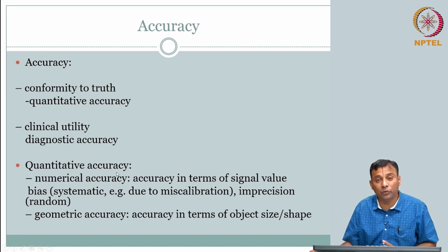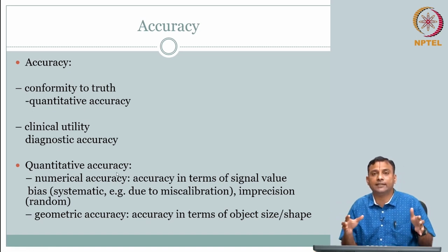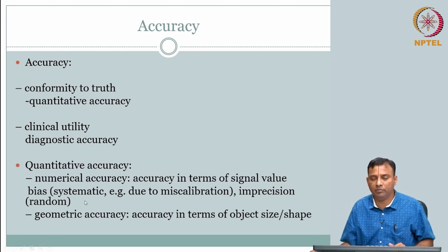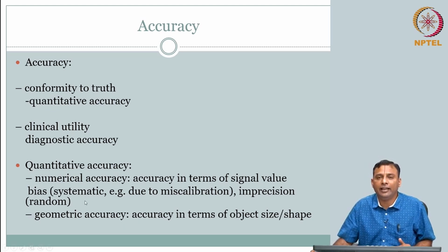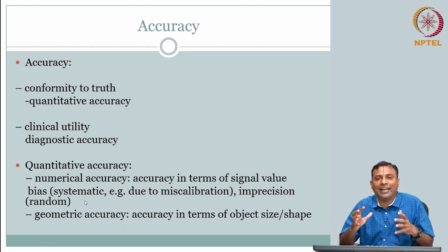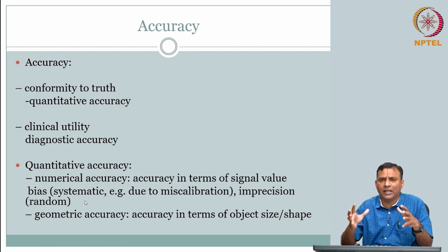That is something you will be involved in as a systems engineer. But these are okay, because you have control over everything. You can have a calibrated phantom. Remember we talked about resolution bar phantoms. You can have a calibrated phantom where every dimension is known, and then you use the system and characterize it. So you can report all this quantitative accuracy and geometry, and correct for it.